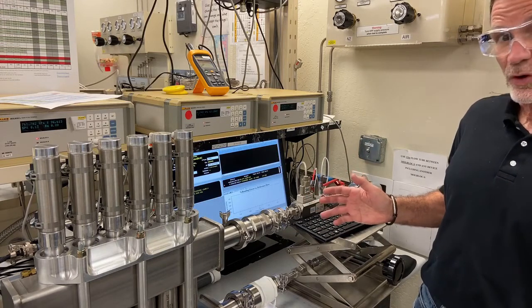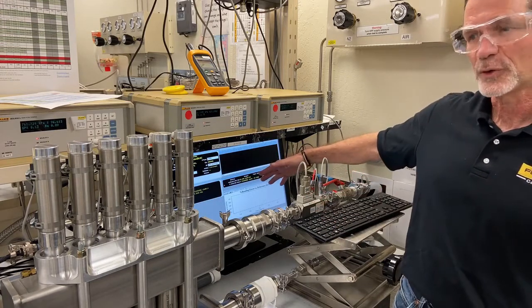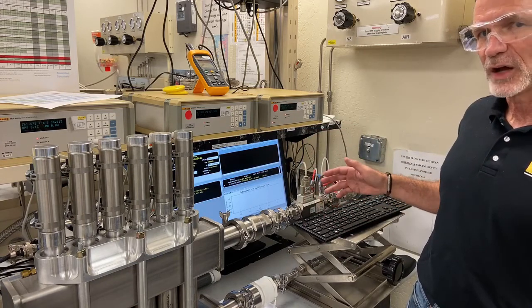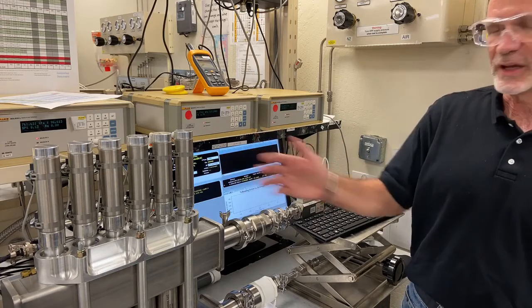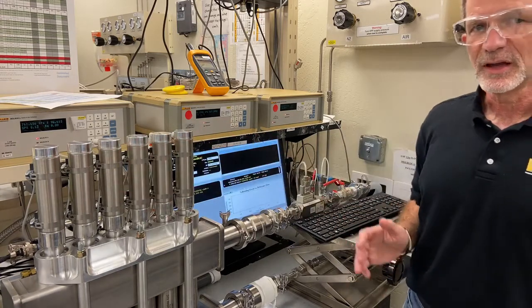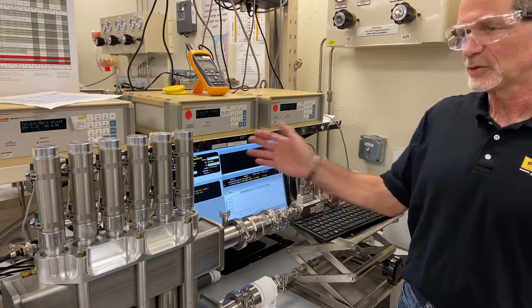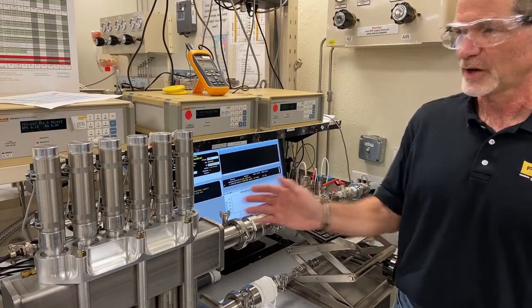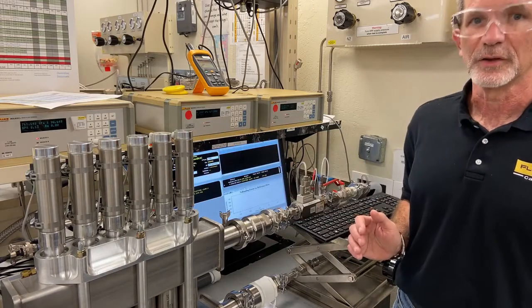What's really cool also is that our Compass for Flow software is not only recording the value of the MolBlock's calculated flow, it's also taking data on the sonic flow element that we're calibrating, and we're using that data to calculate coefficients that the customer will supply or apply to the sonic nozzle when they're using it in the field.